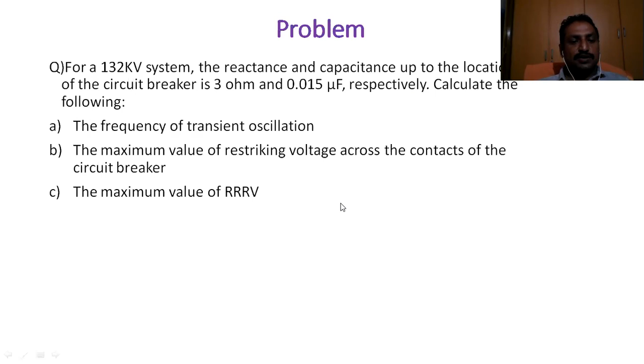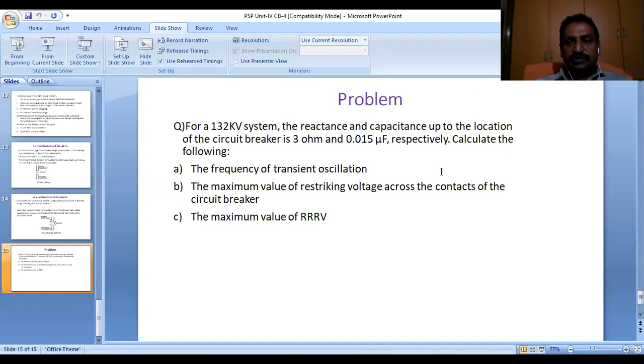Then I'll go through this problem. For a 132 kV system, the reactance and capacitance up to the location of the circuit breaker is 3 ohm and 0.015 microfarad respectively. Calculate the following: the frequency of transient oscillation, the maximum value of restriking voltage across the contacts of the circuit breaker, and the maximum value of RRV. So for this, I'll solve the problem.